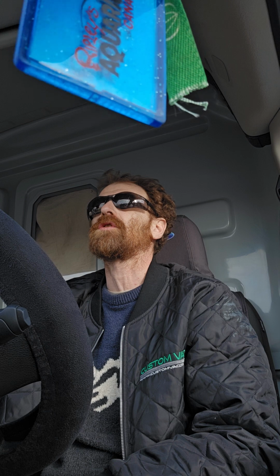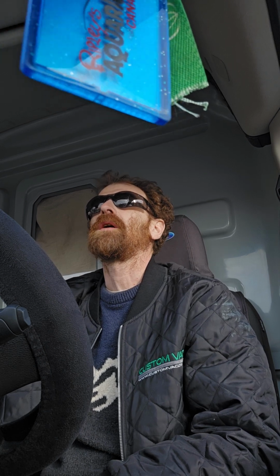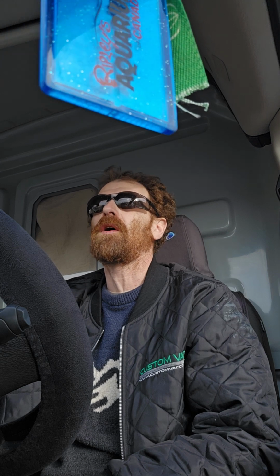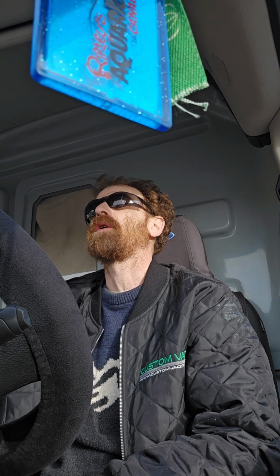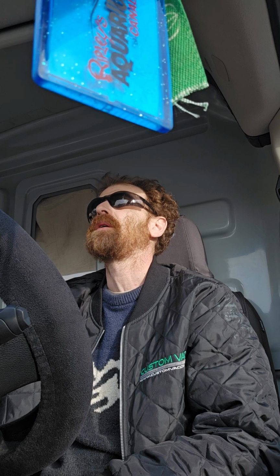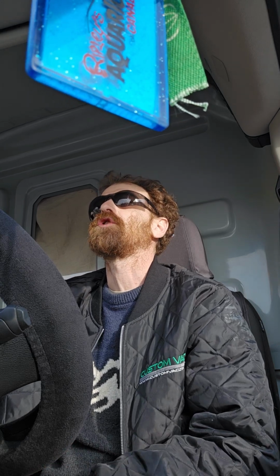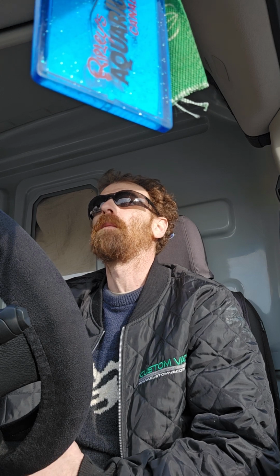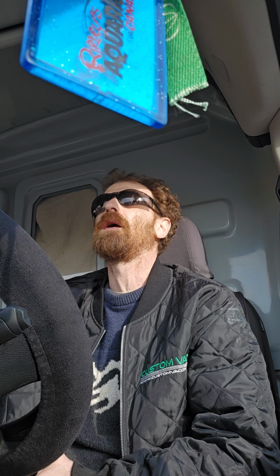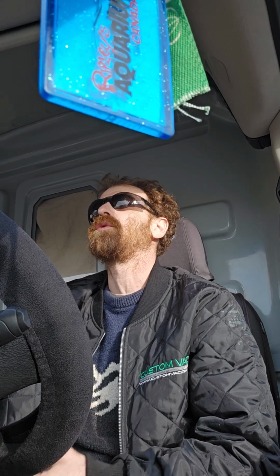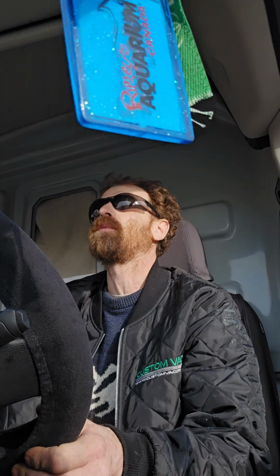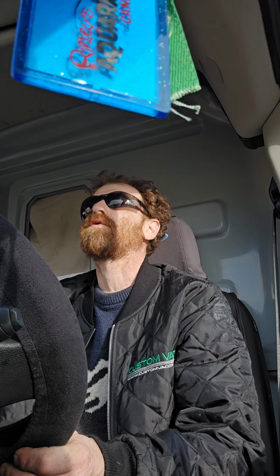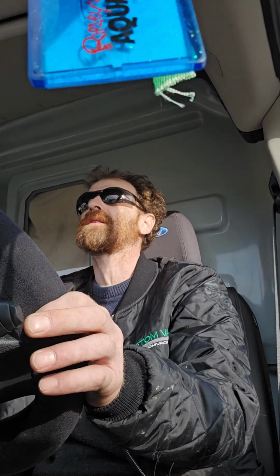You got your thermostat, which is calling for heat or not calling for heat. And a sequence of operation, right? What does the unit do when there is a call for heat? So on this one in particular, we're on an oil furnace, right? The first thing that has to happen is, and because this is an older unit, we get fuel and ignition at the same time. So both the burner motor, which drives your pump, as well as giving power to your transformer, that all happens at the same time when there's a call for heat. And of course that power runs through your stack relay as a safety, runs through your fan and limit as a safety.